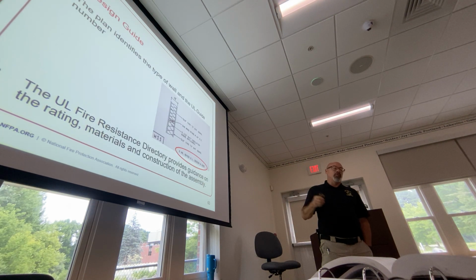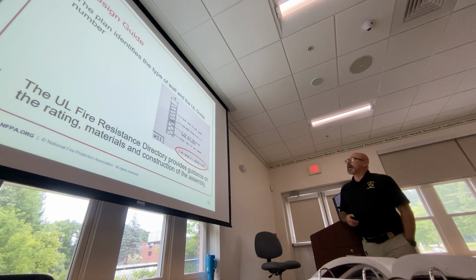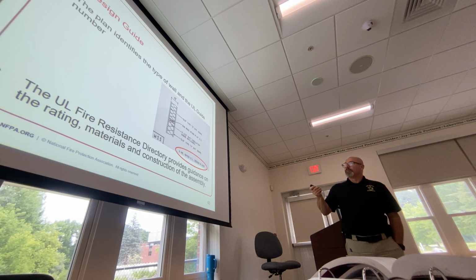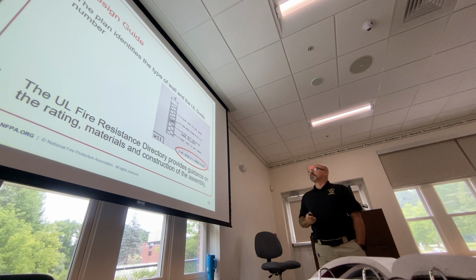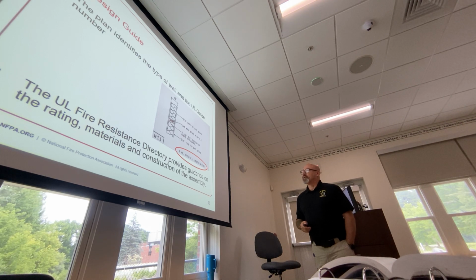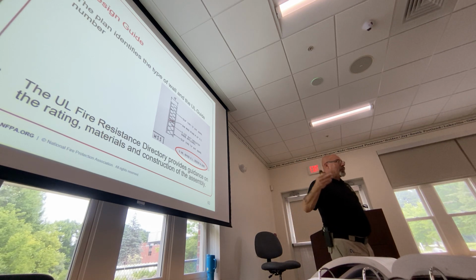Oh, look at that, I didn't have to go searching on the website, but here's a UL design guide. Here's the meat and potatoes right there, or that peanut butter and jelly sandwich I talked about. 2x6 wood studs. If somebody provides you that UL 305 1-hour rating and they're using metal studs, it doesn't meet.